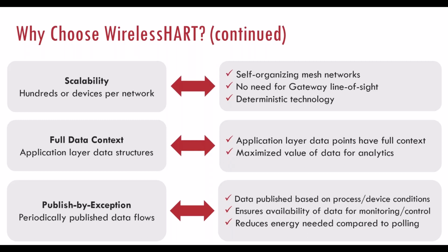We touched on this a bit earlier as well. The application layer data structures have full context, meaning that, in addition to the data received, they also include additional data that maximizes the value for data analytics. Publish by exception. The instruments themselves publish data periodically with a preset periodicity. What this allows us to do is extend the battery life of the field instrument. And we will talk about battery life in a little bit as well.